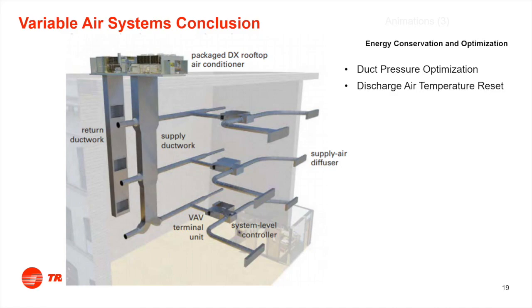We can use duct pressure optimization to reduce the fan speed. We can use discharge air temperature reset to reduce the temperature into the box. Why give it 55 degrees and then reheat it up to 80 if we need to satisfy that space? Go from 55 up to, or from 70 up to 85 or something like that.